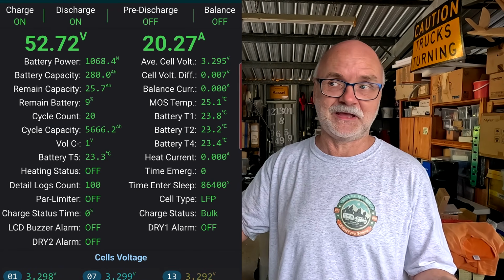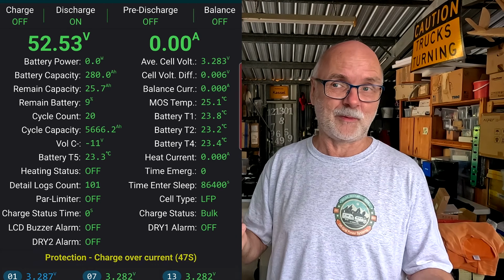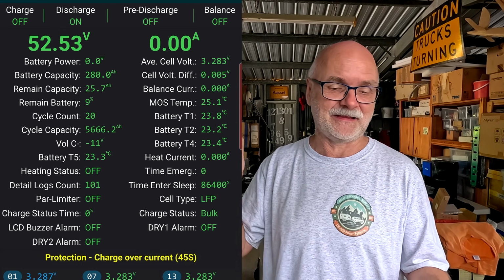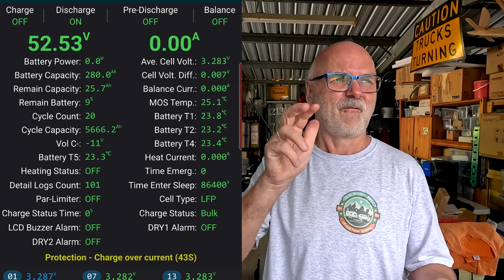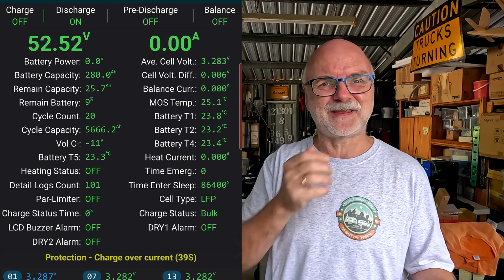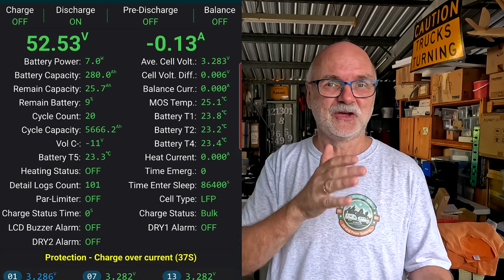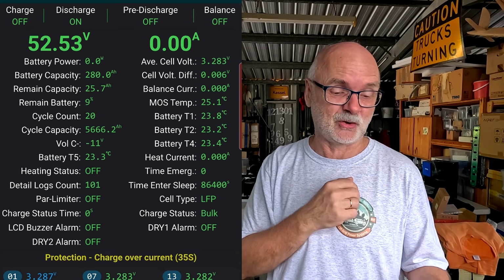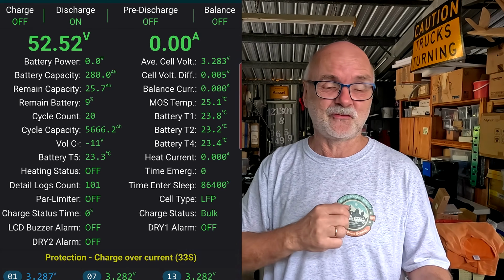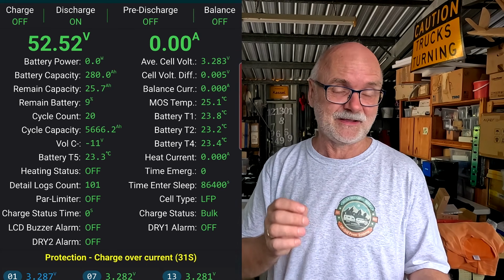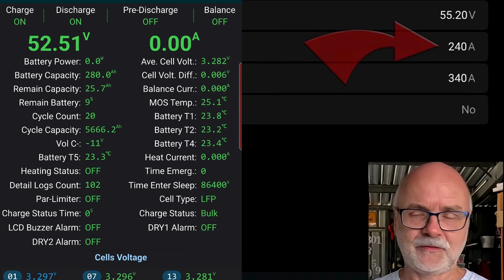This is over current again. So now again, the timer runs for 1 minute and then it tries again and again and again. And I think it tries it a couple of times only before it actually totally resets and then stops charging altogether. And I think it goes into an alarm then, and then you have to reset the BMS manually. And now the alarm clears again.